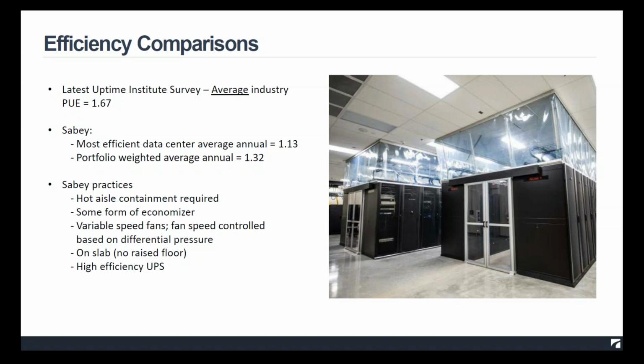In all of our data centers, we use variable speed fans, and the fan speeds are controlled based on differential pressure. So essentially what we're doing there is we're trying to match the amount of fan energy we use, the amount of airflow that is being moved through our air handlers, with the amount of air that's being moved through the servers by the server fan. So that's that ideal situation where you're moving just as much air as the server fans are moving, and you're not seeing the bypass and the recirculation air that Steve mentioned in his presentation. Now we don't meet that ideal, but we come pretty close in a lot of our data centers to eliminating that bypass and recirculation air.